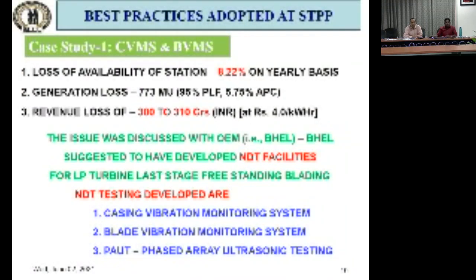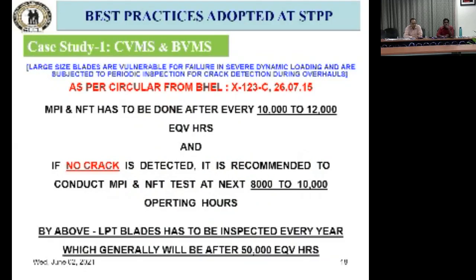When we took and commissioned this, BHEL gave a circular number X123C. As per the circular, BHEL recommends that MPI & NFT has to be done every 10,000 to 12,000 equivalent hours. And if no crack is detected, it is recommended that MPI & NFT be done after 8,000 to 10,000 hours, which is just a little above every year.